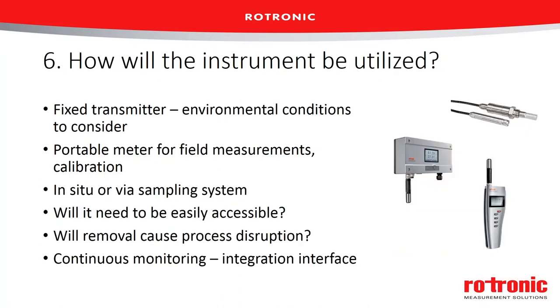Number six: how will the instrument be utilized? This may seem straightforward but it's not. Will it be a fixed transmitter? Think about the environment where the transmitter and its electronics will be stored. For example, if you're measuring in Antarctica and you have a fixed transmitter with an LCD display outside at minus 40 degrees, that LCD is not going to work. Will you need to take the instrument to different places, requiring a portable instrument? Will you need to measure in situ inside your process or compressed air system, or take a sample off-site? That requires different fittings, instruments, and probes.